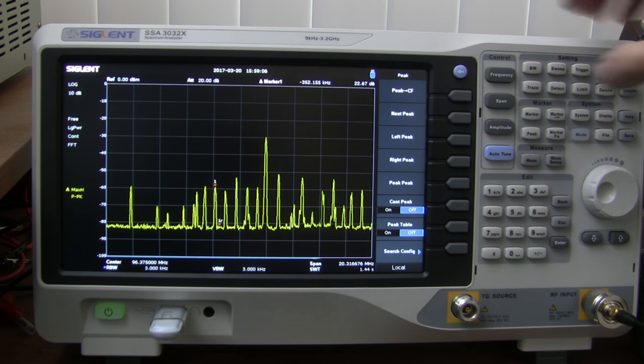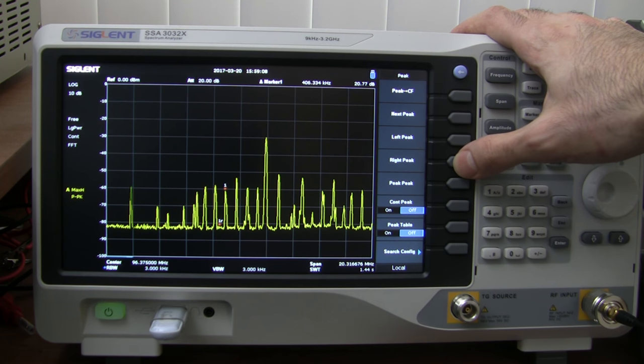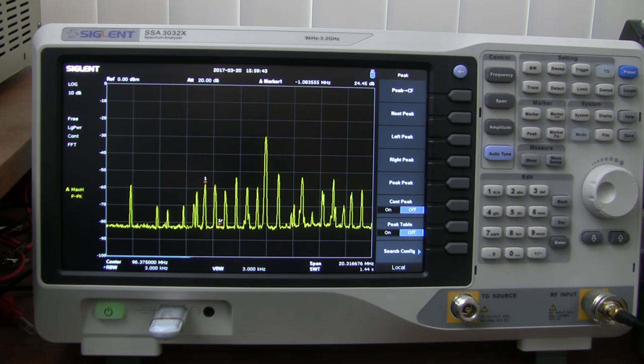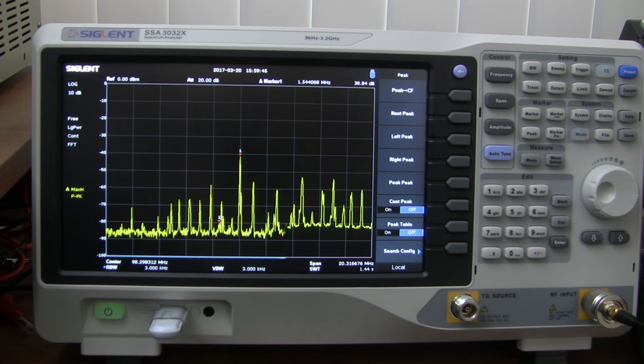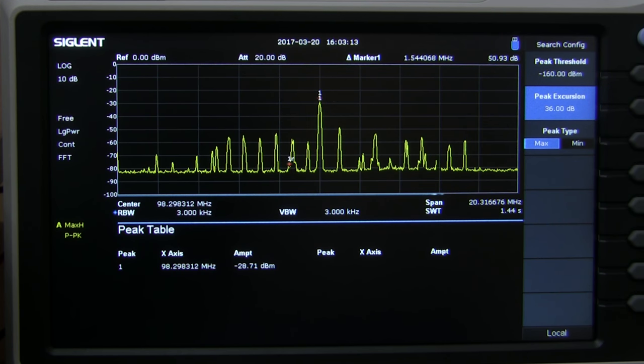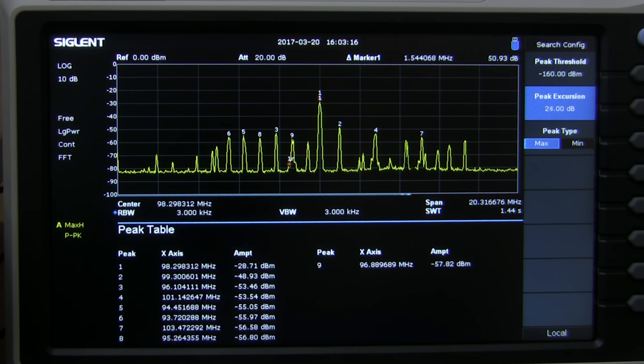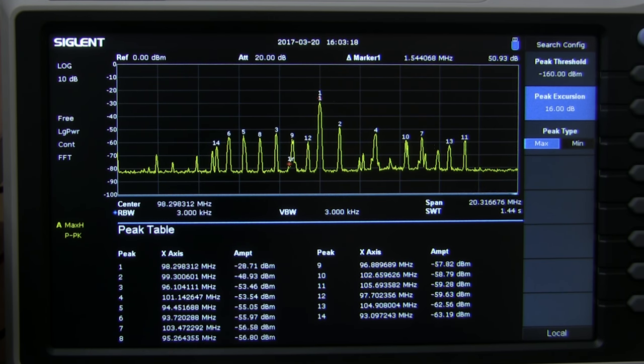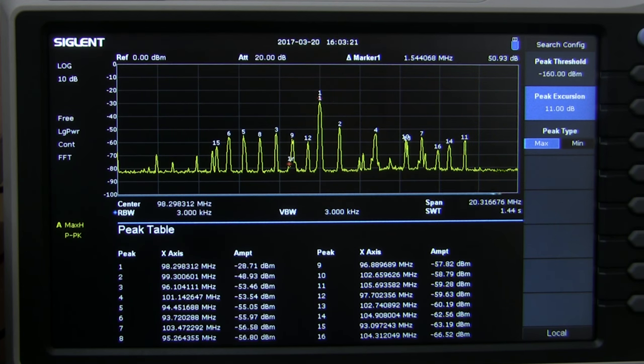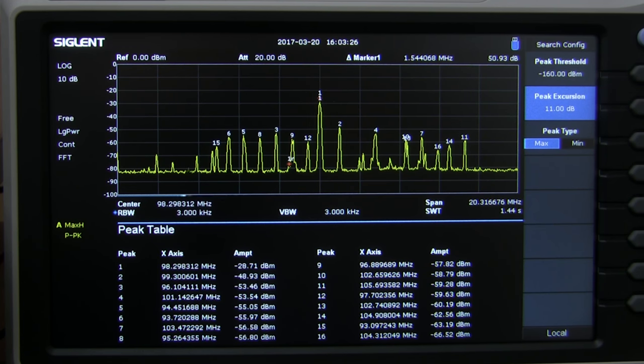If we go to the peak menu, I really like how the peak search navigation works. And I really like this peak to center frequency shortcut, it's a huge time saver. Now check this out, you can manually change the threshold above the noise floor for which a peak gets registered. The peak table feature works well, and it lets you see up to 16 peaks at the same time. Unfortunately there's no way to display the frequencies on top of the peaks themselves.